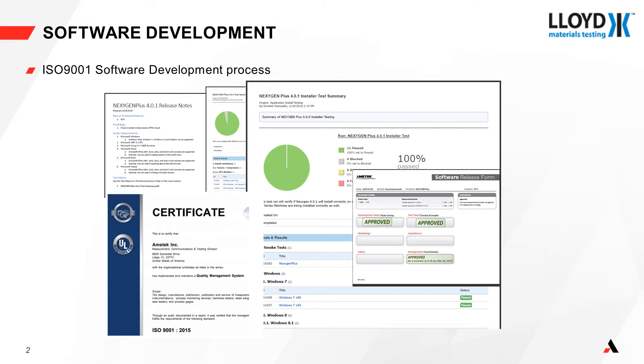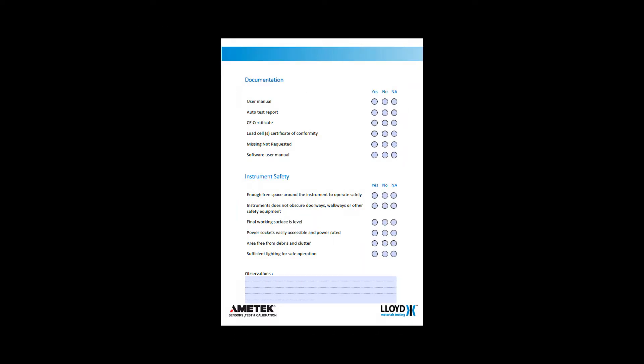Data integrity begins with the design and development process. At Ametek Lloyd Instruments, our rigorous ISO 9001 procedures validate that the equipment produces repeatable and accurate data. Our installation and operational qualification services verify that the hardware and software are functioning as designed and producing accurate data.